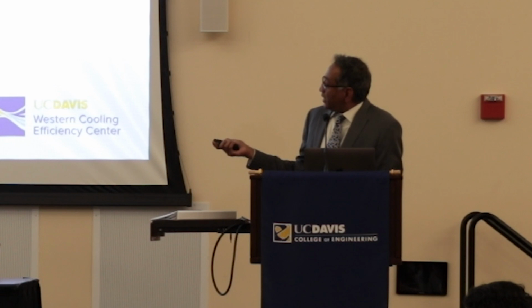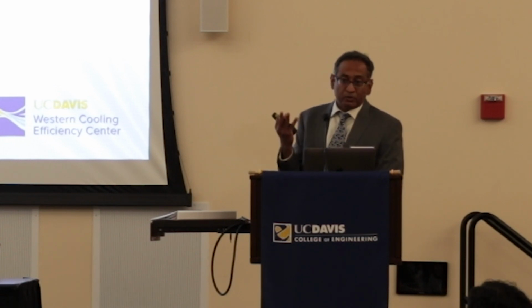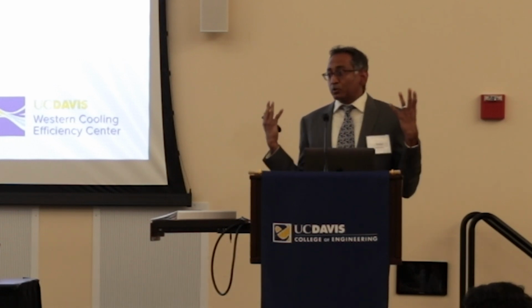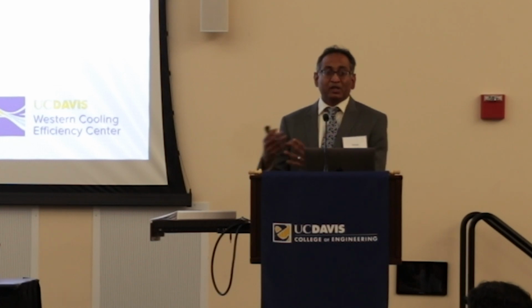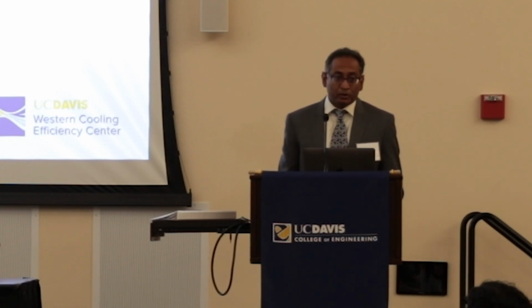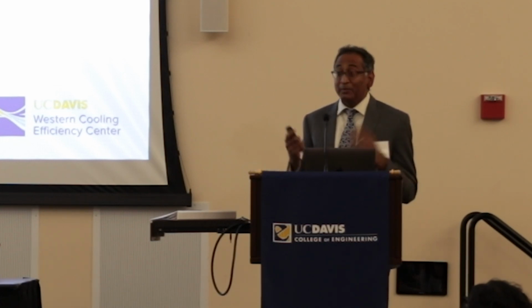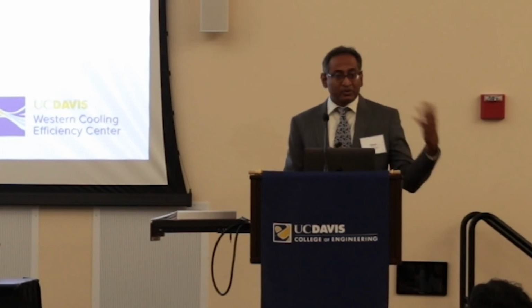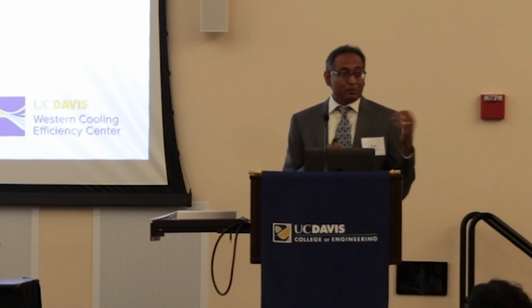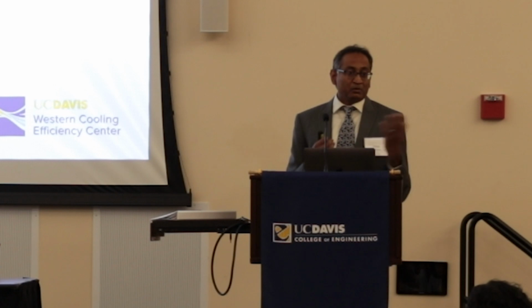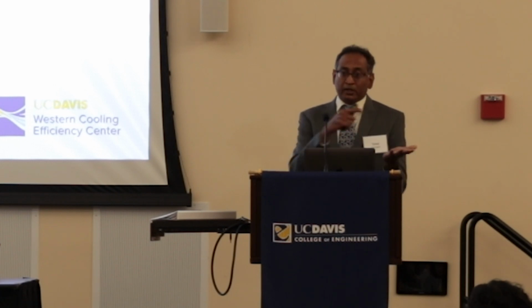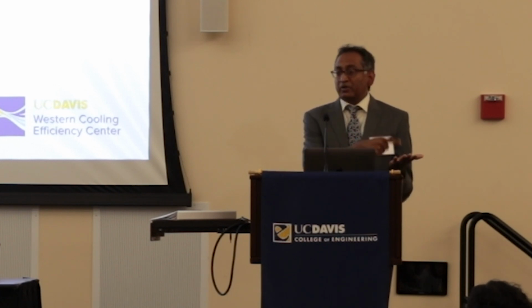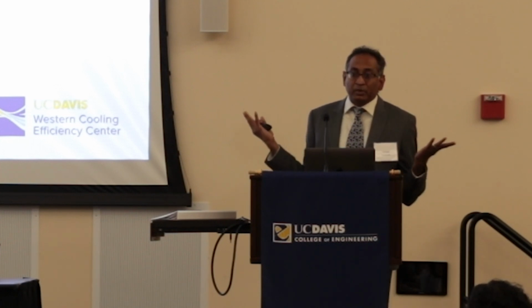So ARPA-E has a challenge for us engineers, and they told us, can you reduce the energy used for cooling? A lot of energy is used for cooling in these data centers. They just cool down the entire data center room so that if you walk into a data center, you've got to go with a thick coat. It's that cold. And there are better ways to do it. The chips, CPUs, GPUs can handle high temperatures. So why do you need to cool the entire data center down? Why can't you go to the source, which can handle temperatures of 80 degrees Celsius, extract heat from there, and just dump it in the environment? At best, it's going to be at 45 degrees.